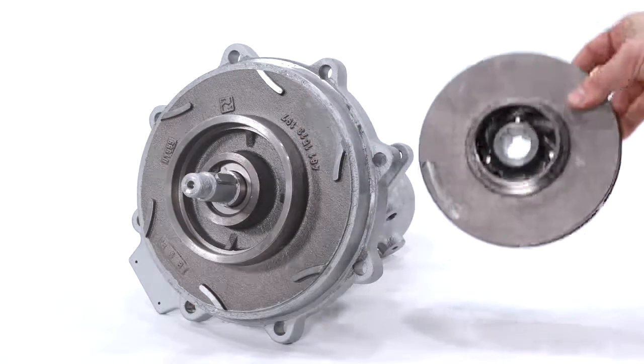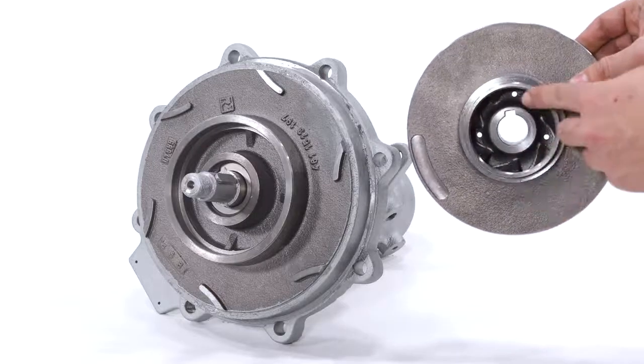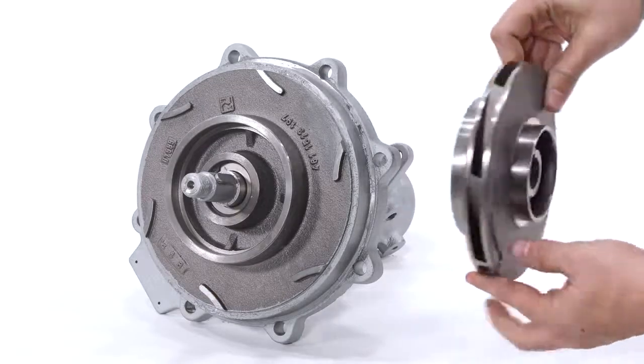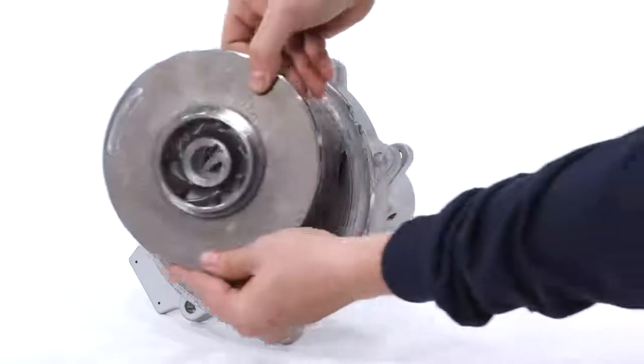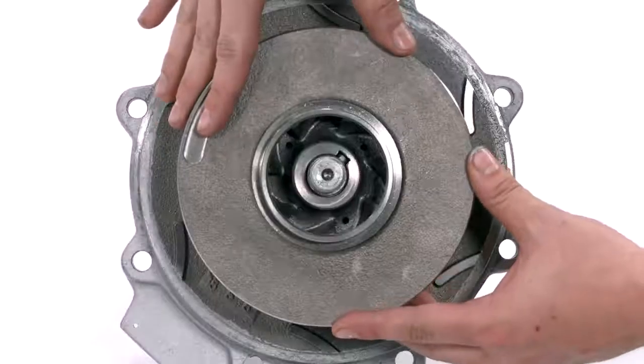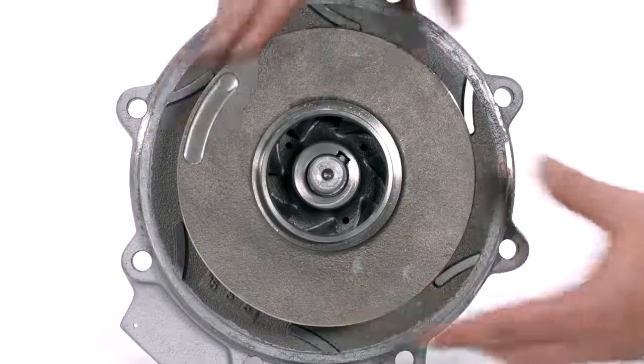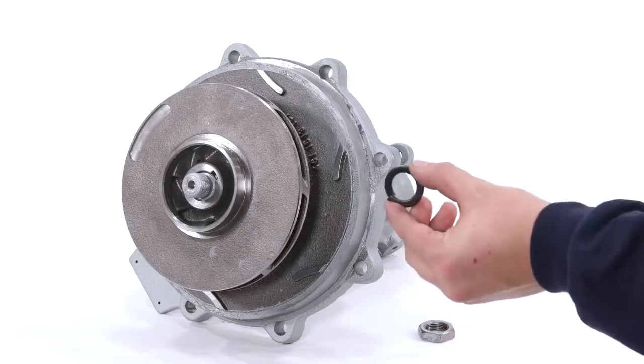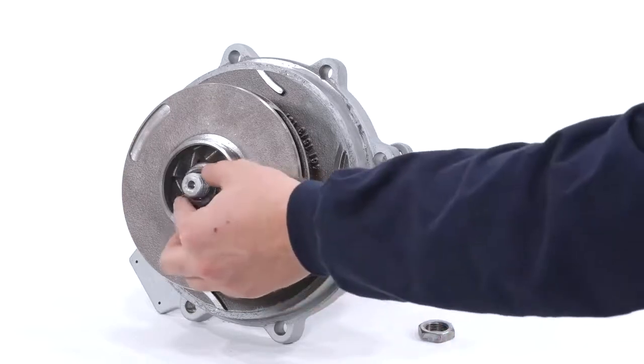Install the impeller, in the correct orientation, onto the shaft. Install the impeller lock washer and nut and tighten with a 30mm wrench.